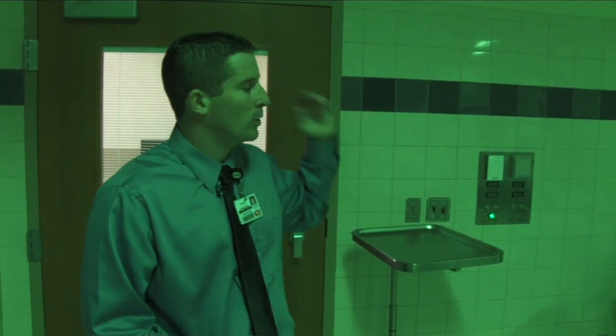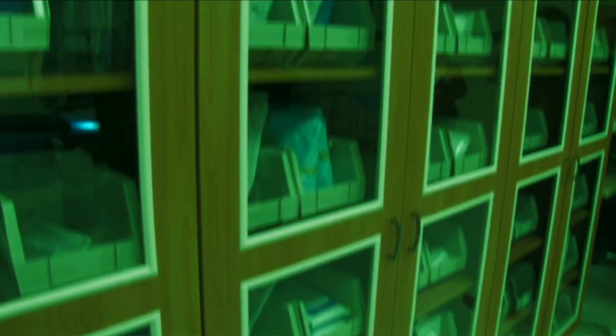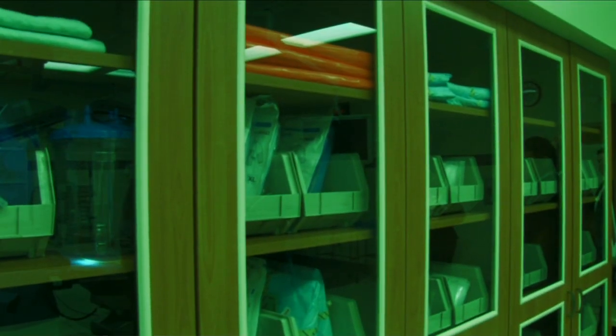And what that tells us is, for the safety of the patient and for infection control reasons, that we have enough positive pressure to keep germs and everything else outside the room. And if the doors are open and we're not maintaining that positive pressure, this will alarm. It will alarm all the way down the main corridor here until the room is closed and that pressure is built back up. The cabinets and everything are on the left side of the room when you come in.